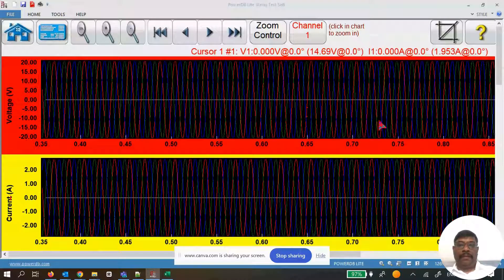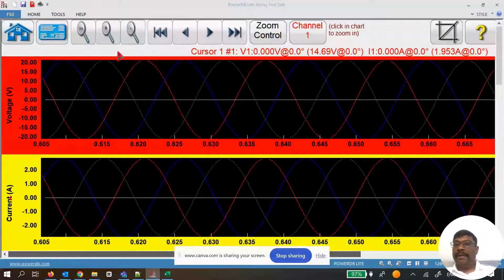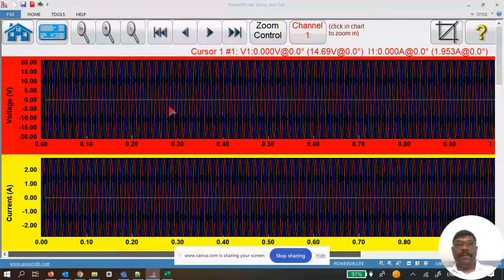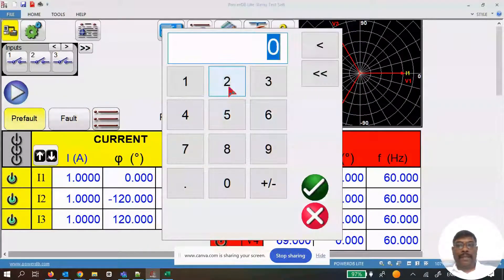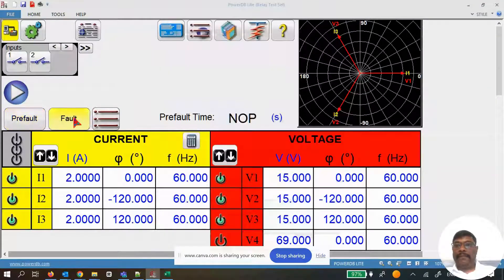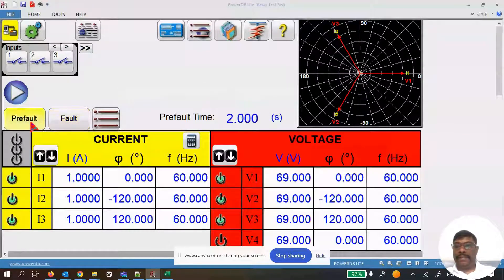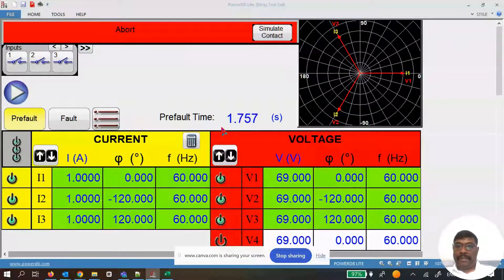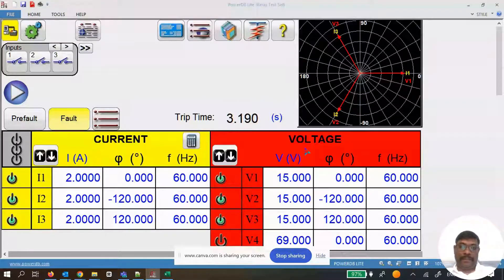In the waveform view, I can see the pre-fault and fault, but I forgot to define the fault time in the previous test, which is why it only shows one second of fault duration. I go back to the home screen to correct this: I set pre-fault to two seconds and fault time to infinity so we can see the fault continuously injecting. I press Play — the pre-fault injects for two seconds, then the fault injects continuously. I simulate contact and stop the test.